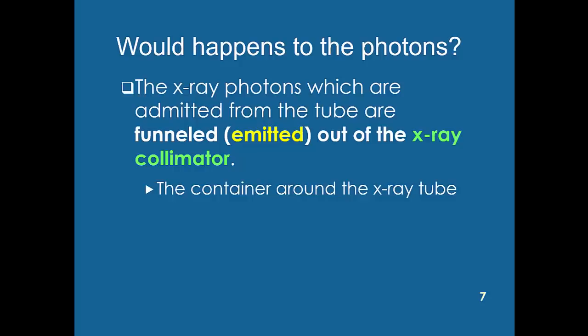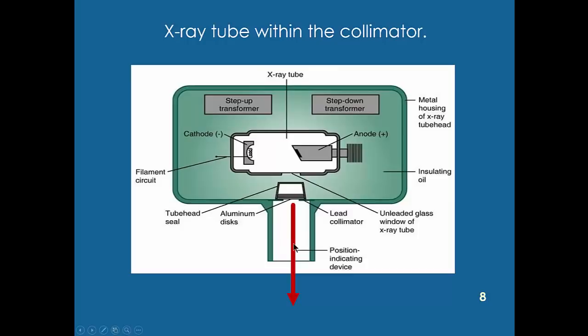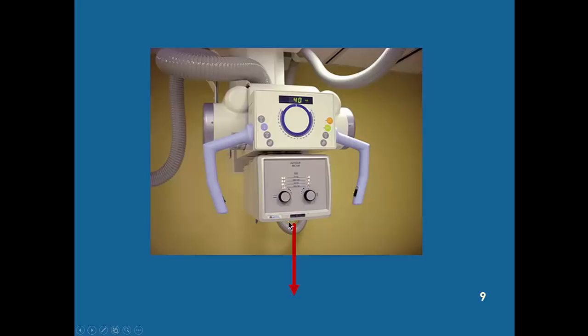The photons fly around inside the x-ray tube, but something called the collimator contains and funnels them out the front — almost like the barrel of a gun. Here's the x-ray tube with a cathode and anode; the green thing is the collimator. You can aim this whole assembly: if you want to take a picture of someone's wrist, you aim it at the wrist. You can also narrow down the beam using the collimator's lead shields so you don't blast the whole arm.